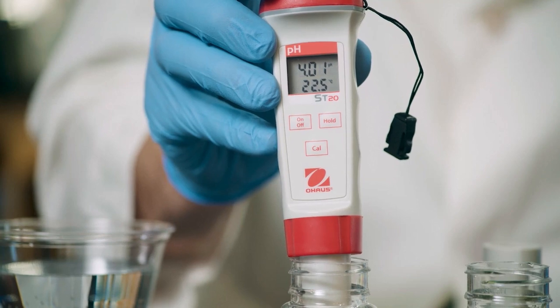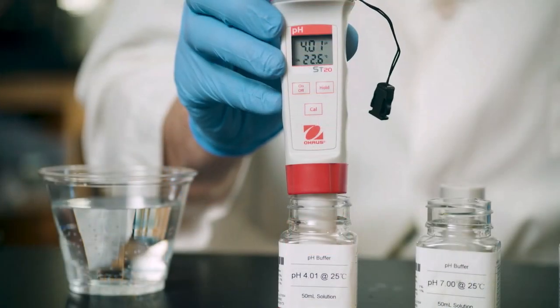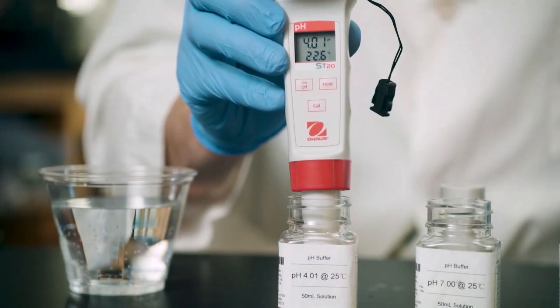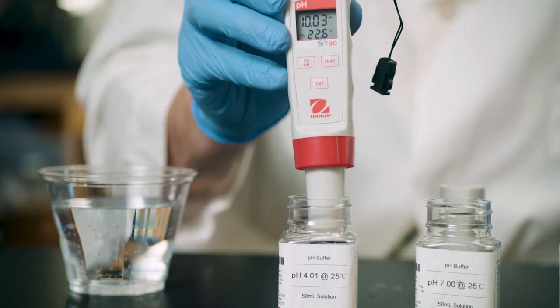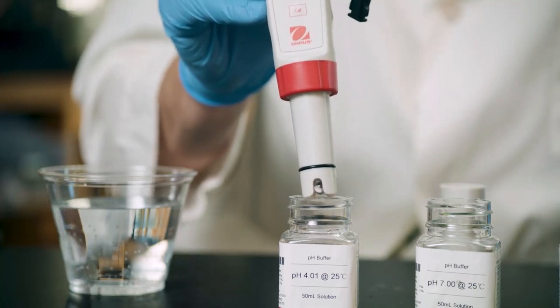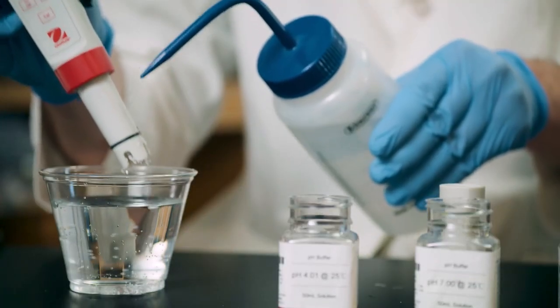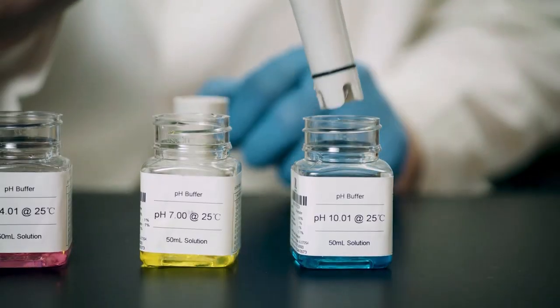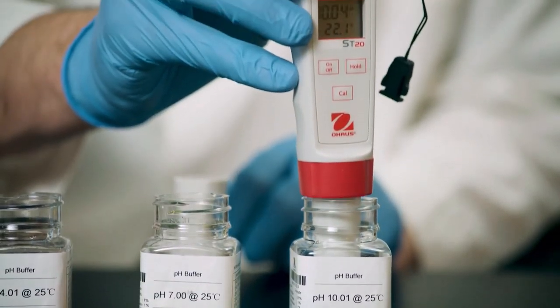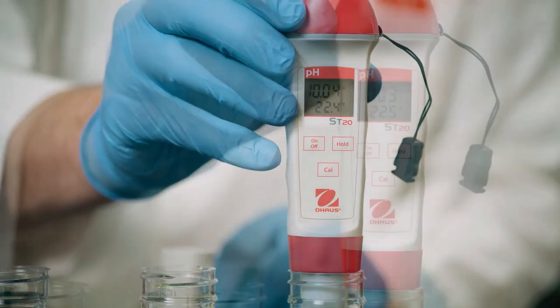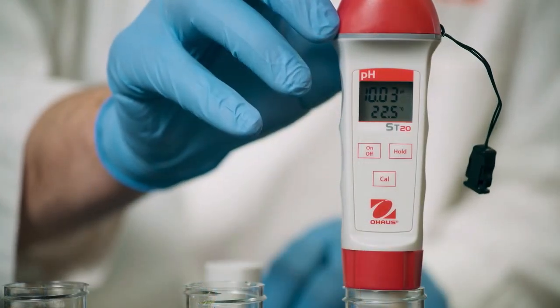Once Cal stops blinking, the display will change to approximately 10.01, indicating that the meter has been calibrated for 4.01. Remove the probe, clean the electrode with distilled water and insert it into the 10.01 pH buffer solution. Wait for Cal to start blinking and stop blinking. Upon completion, the Cal will disappear.